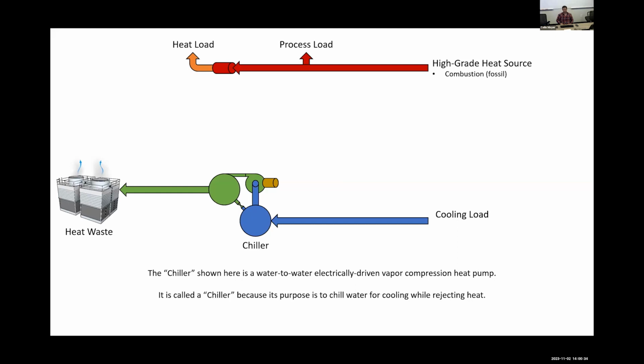And the chiller is actually a heat pump. That chiller is taking waste heat from the buildings at a colder temperature, and it's raising its temperature so that we can reject it. We usually use evaporative cooling towers in larger systems, but essentially the heat is absorbed from the building using a low temperature medium, which is chilled water. And then the chiller is a heat pump that raises the temperature to above ambient conditions so that we can get that heat outside.